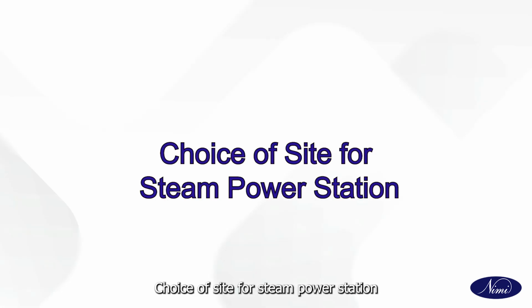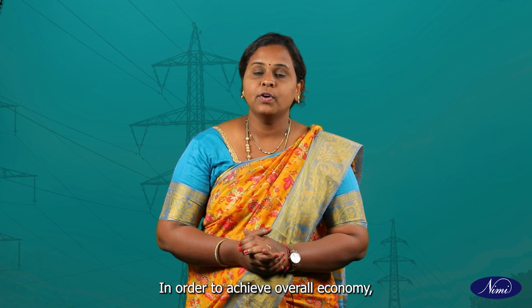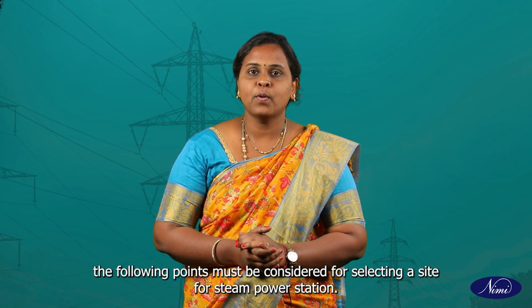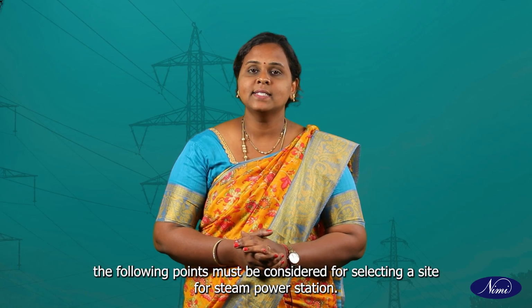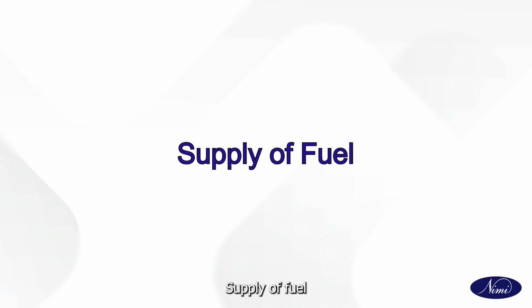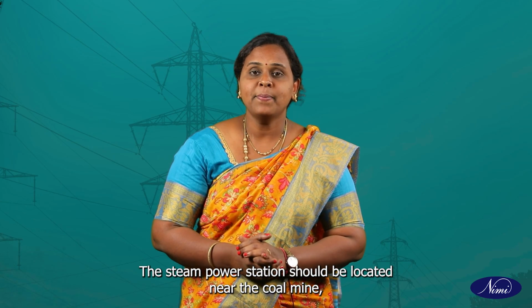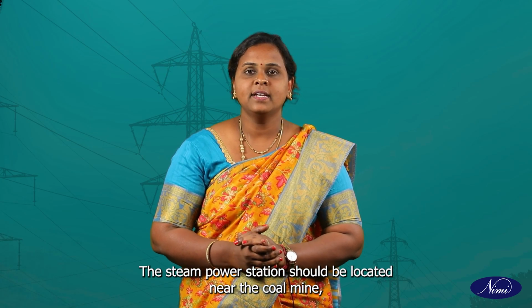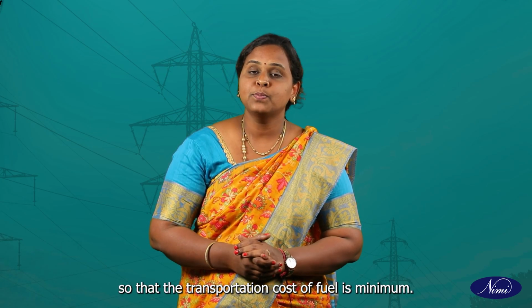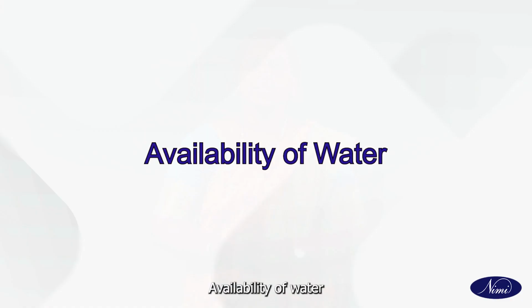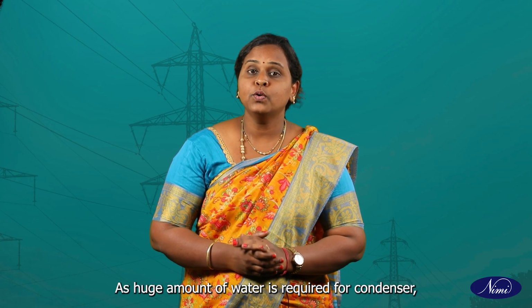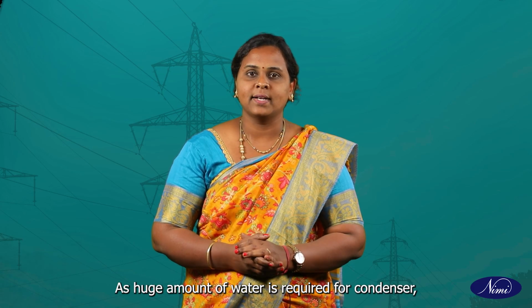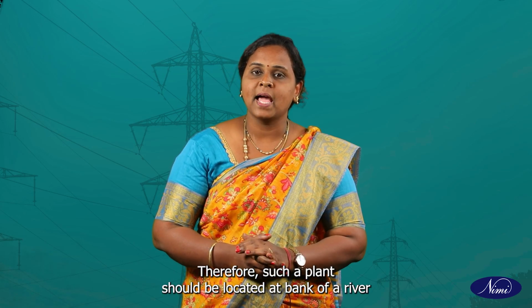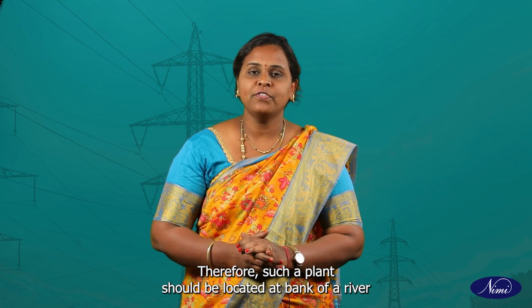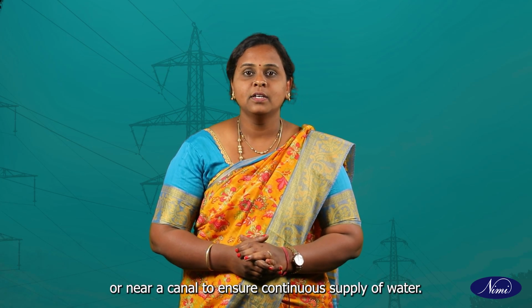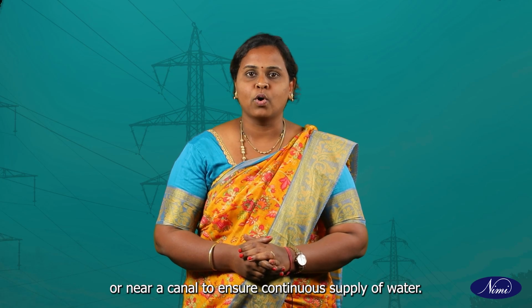Choice of site for steam power station. In order to achieve overall economy, the following points must be considered for selecting a site for a steam power station. Supply of fuel. The steam power station should be located near the coal mine so that the transportation cost of fuel is minimum. Availability of water. As a huge amount of water is required for the condenser, such a plant should be located at the bank of a river or near a canal to ensure continuous supply of water.